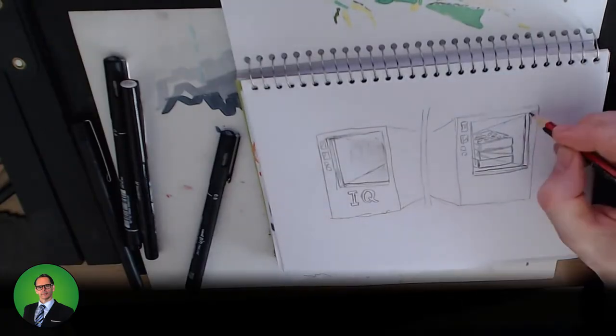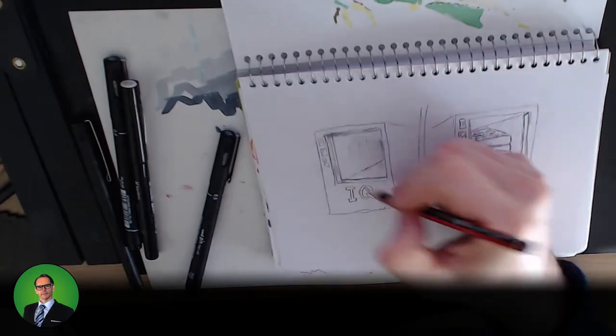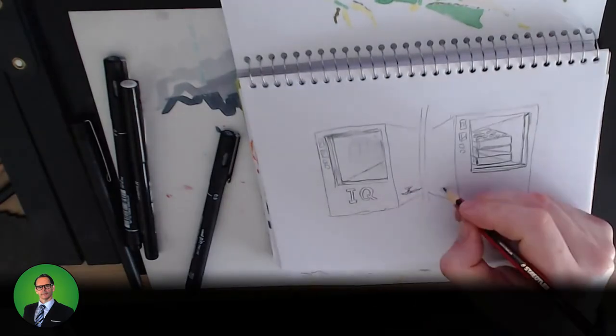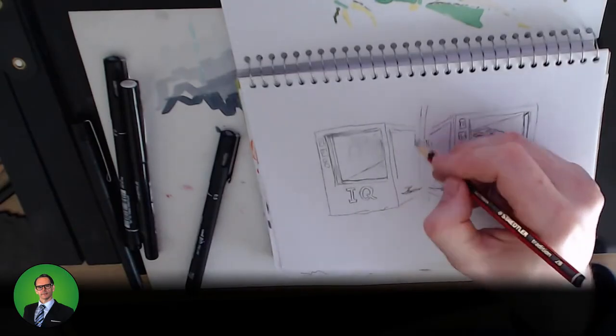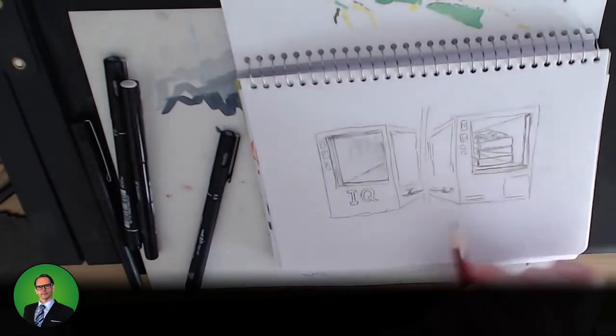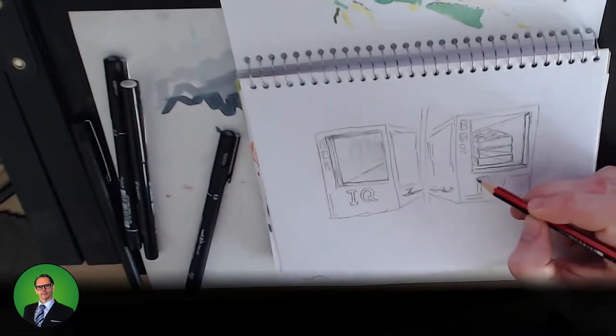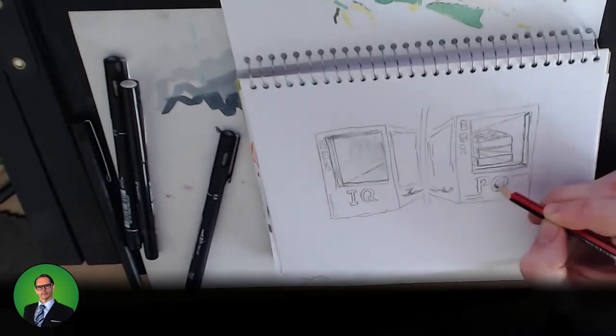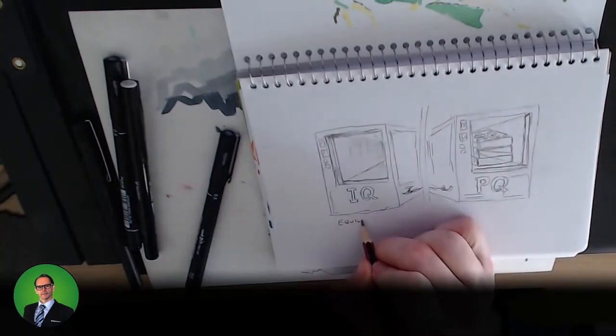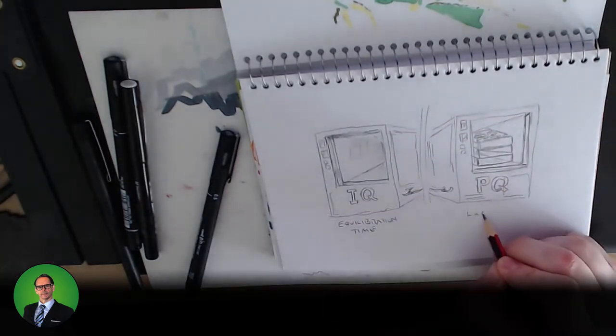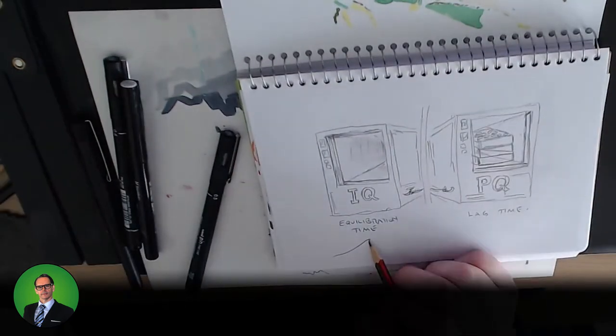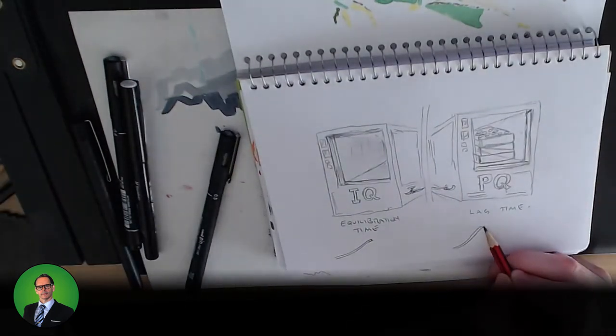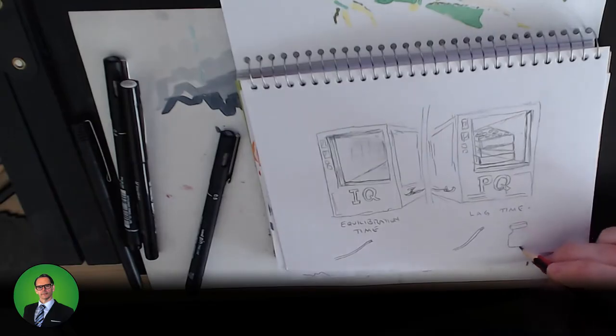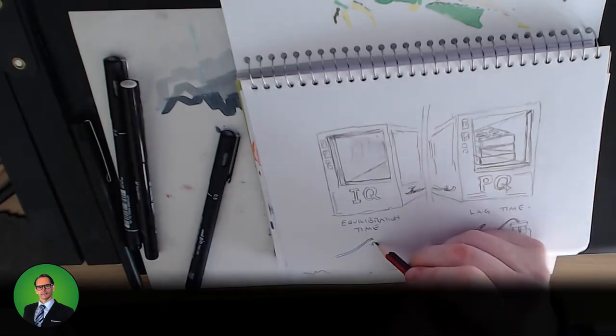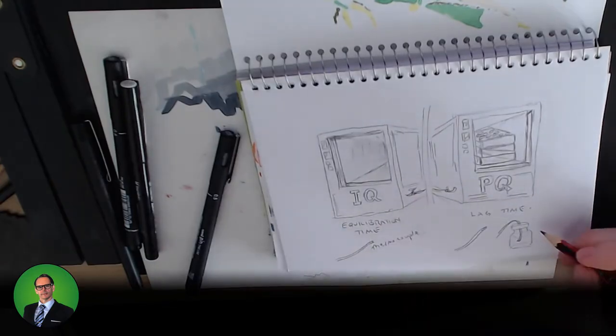And I'm using this image to just contrast where you would use equilibration time, which in a nutshell is during your OQ, so an empty autoclave chamber, and when you would worry about latency or lag time for your thermocouples, which is during your loaded cycle, so your autoclave pattern validations, which forms part of your performance qualification. So I might as well chat a little bit about that here, but I'll go into a bit more depth in the specific science themed video.